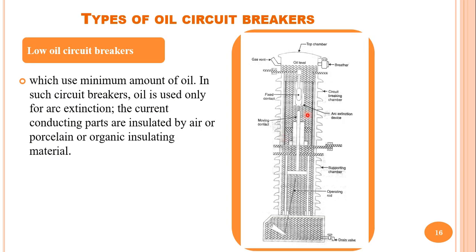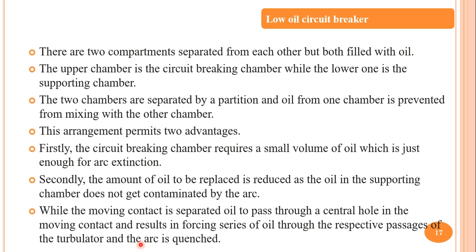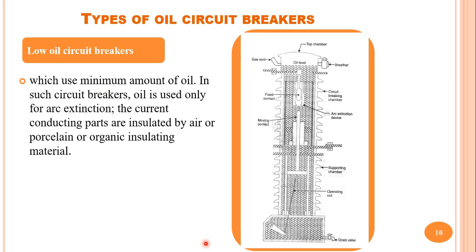The arc is mainly produced in the top chamber, so only a small portion of oil needs to be replaced after the operation of the circuit breaker. When the moving contact is separated, oil passes through the central hole in the moving contact, forcing a series of oil jets through the passages of the turbulator, and the arc is quenched. The moving contact is a hollow cylinder and oil is passed from the moving contact to the arc path, extinguishing the arc.